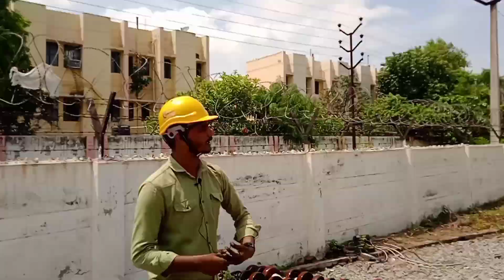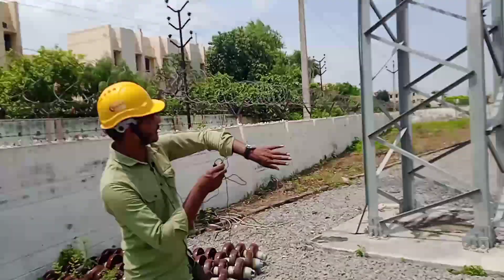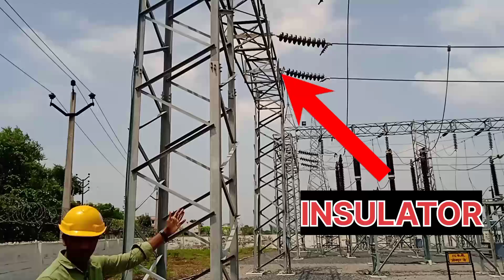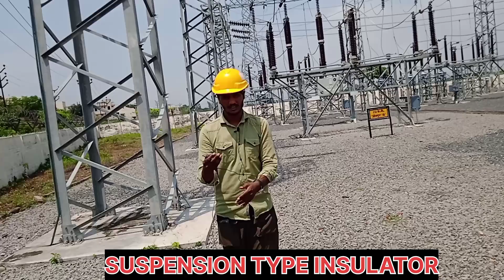Here you can see a lot of insulators available. One disc of this insulator is 11 kV, so you can calculate. These insulators are available there. This is a strand type insulator - when the insulator is vertical it's called a suspension type insulator, and when the insulator is horizontal it's called a strain type insulator.